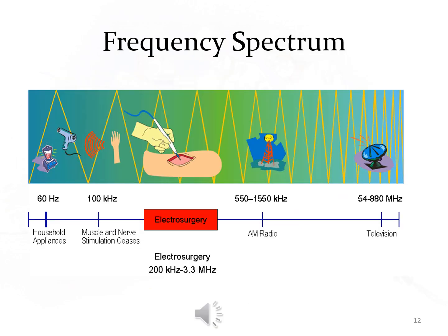The frequency used for electrosurgery must be sufficient to cross the tissues but without activating the muscles. Such a case would cause muscle contraction, preventing the surgeon from working, and it is likely to cause the patient's heart to stop.